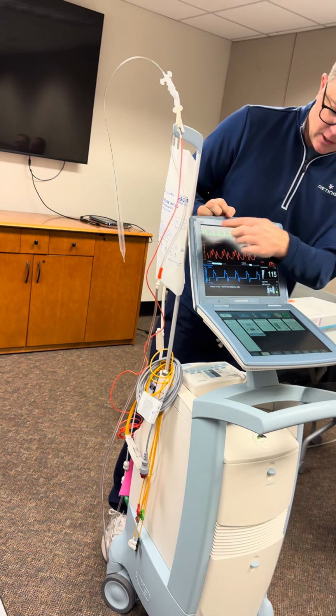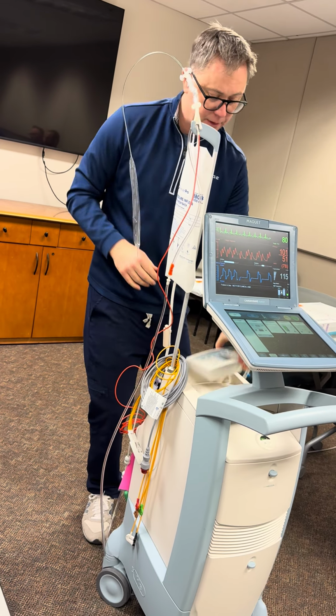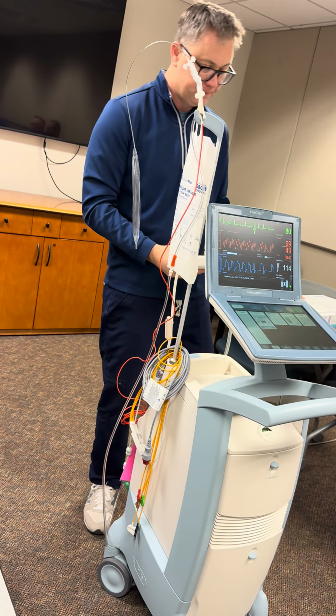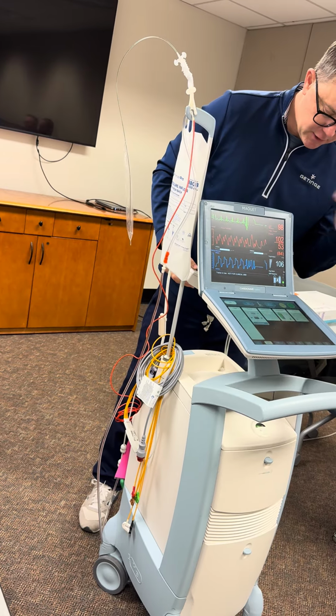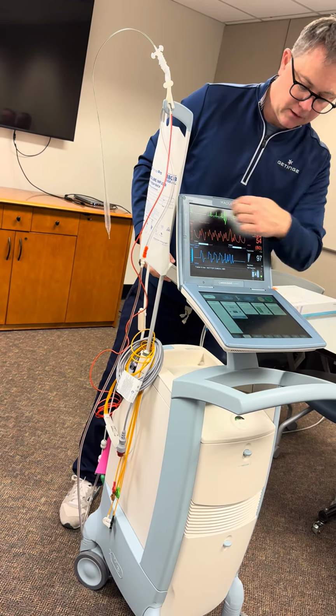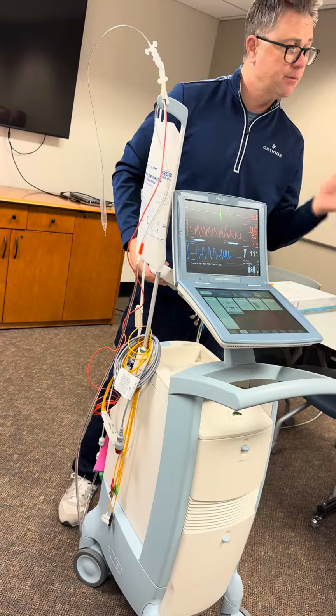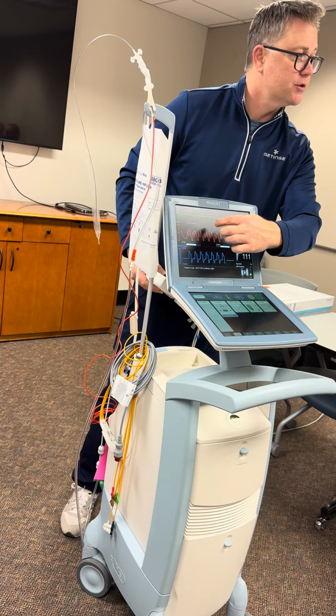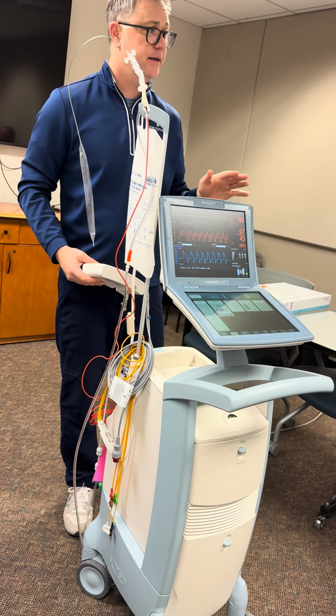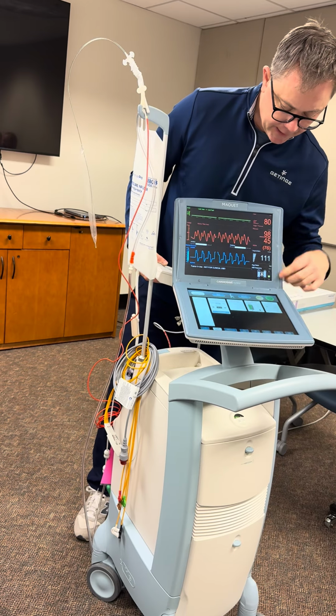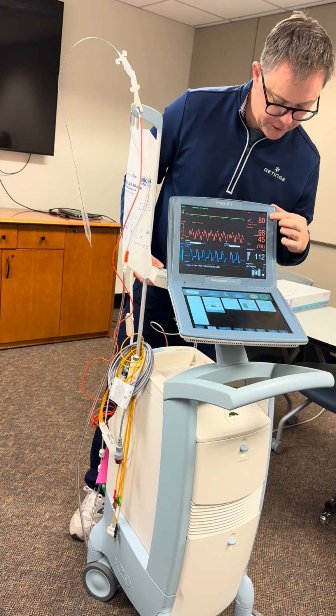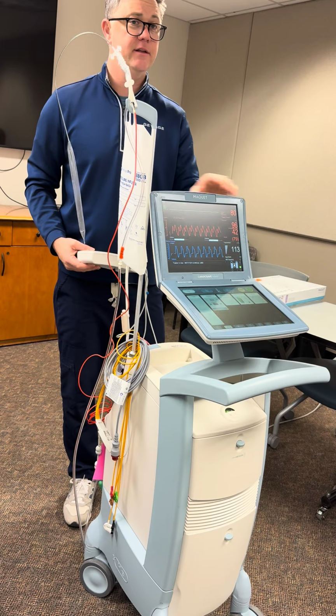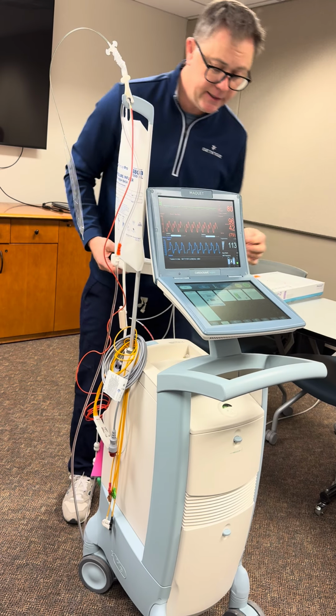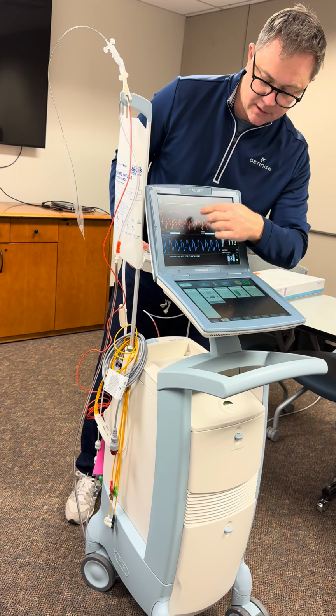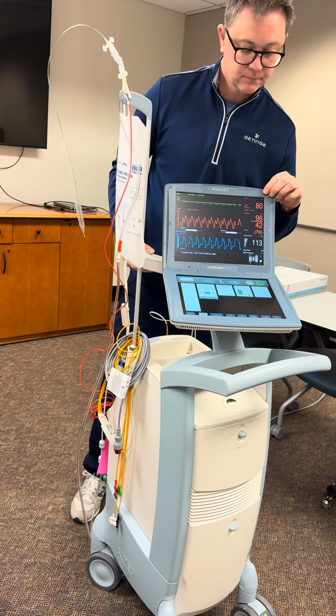Primary trigger is our ECG tracing. If for some reason we lose our ECG, patient's thrashing around, lead pops off, balloon pump's gonna look for an R wave, didn't see an R wave there for a couple beats, and it automatically switched over to the pressure trigger. So the balloon pump does that automatically. It's just a safety feature that's built in. Again, now we're running in what we call our pressure trigger. Totally safe to run the patient in there. We've lost our EKG lead. Now it's looking for the upstroke of systole on the arterial pressure waveform.